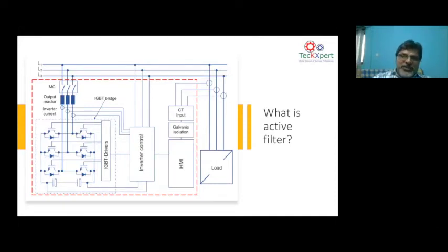Now you can also select it as a selective filter. If you say I want to remove only the 5th, 7th, 11th, 13th, you can select them individually and program the filter, and the filter will automatically take all of that out. So it's a far simpler concept when it comes to mitigating harmonics.